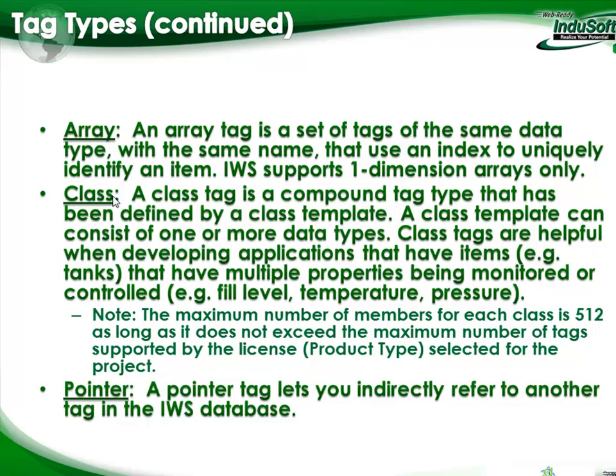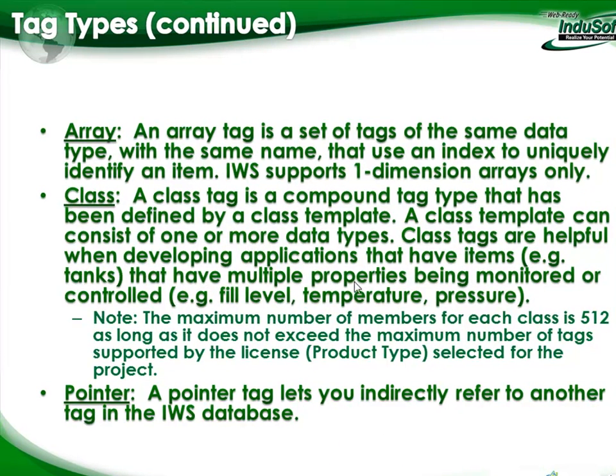A class tag is a compound tag type defined by a class template. The template can include one or more different data types within the class — some reals, some integers, some strings, and so on. Class tags are helpful when developing applications with items such as tanks that have multiple properties being monitored or controlled, such as level, temperature, pressure, or contents. The maximum number of members for each class is 512, as long as it doesn't exceed the overall tag count supported by your license.